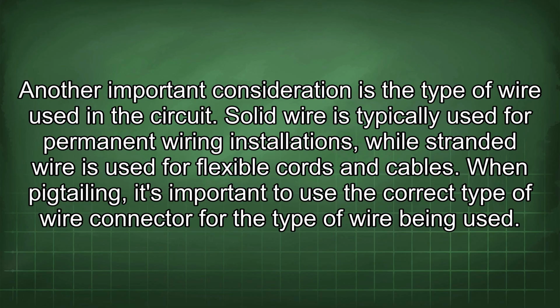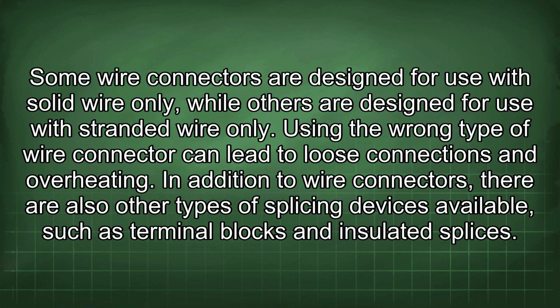Another important consideration is the type of wire used in the circuit. Solid wire is typically used for permanent wiring installations, while stranded wire is used for flexible cords and cables. When pigtailing, it's important to use the correct type of wire connector for the type of wire being used. Some wire connectors are designed for use with solid wire only, while others are designed for use with stranded wire only. Using the wrong type of wire connector can lead to loose connections and overheating.